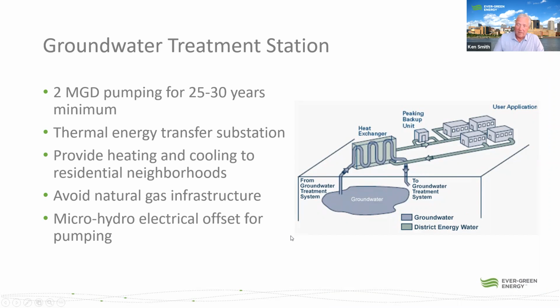The temperature of that aquifer water coming up is very stable and doesn't vary much over a year. So we looked at how much energy was in that groundwater and how we could use it. After the treatment, you'd run the water through a heat exchanger and utilize it either to take heat from it and lift it up, or to reject heat into it as it goes back into the groundwater treatment. It would provide heating and cooling to residential buildings and many others, and this site would be able to avoid putting in natural gas infrastructure altogether. Because you're constantly moving that water, you could also look at some micro hydro to generate electricity on that site.